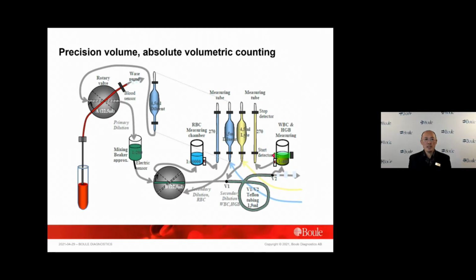So here we can see the RBC and WBC chambers finally get the final diluted blood ready for measurement. The measurement is performed by an even pressure from a slave pump. It is a passive pump to ensure the pressure applied inside a closed chamber is constant and mild, to make a laminar flow of cells through the aperture.